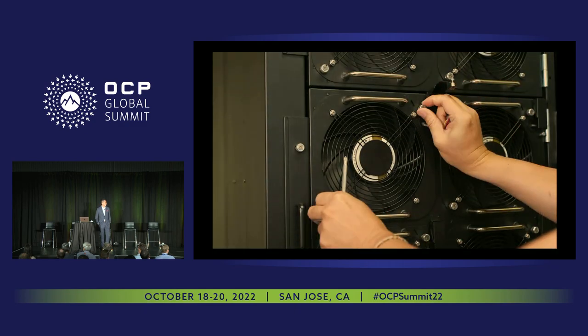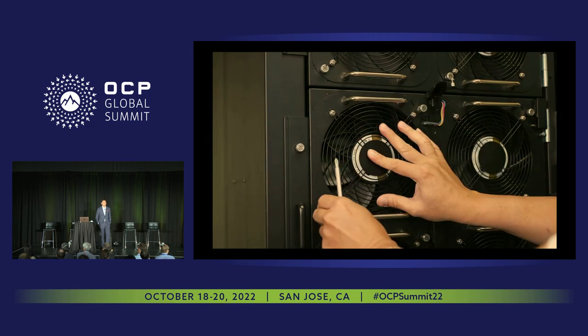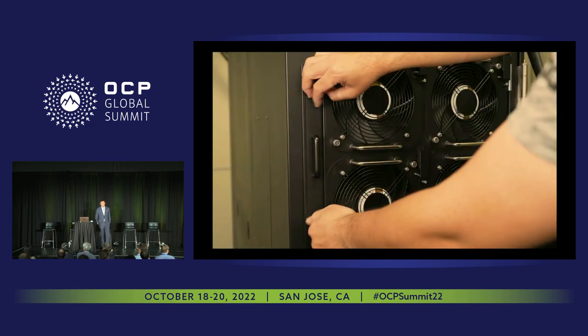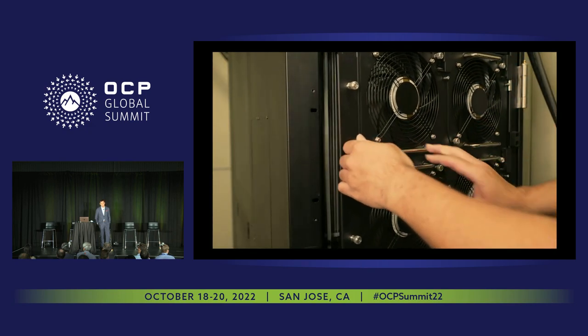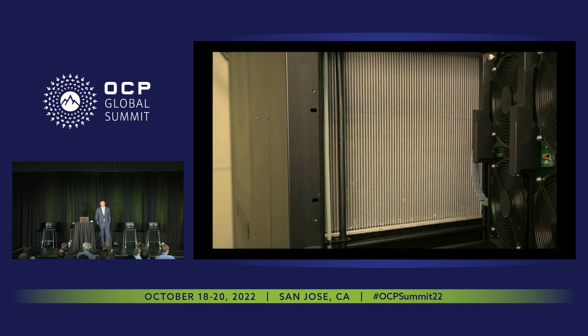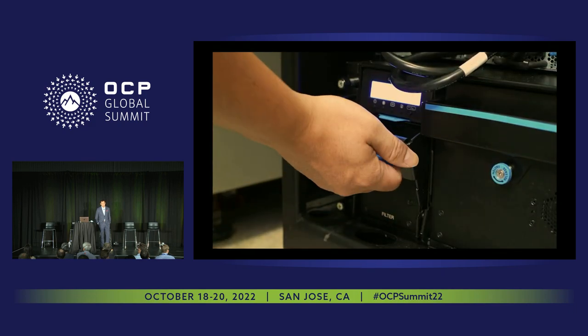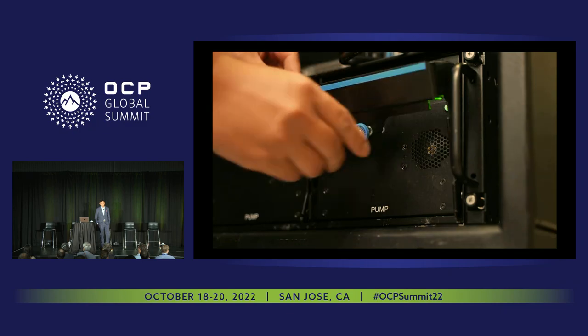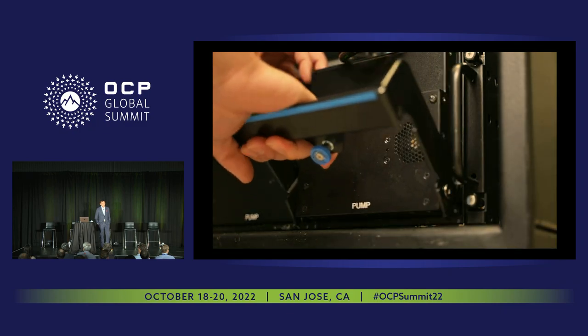And for serviceability, each individual fan can be taken out, and 4 fans are grouped into 1 fan board where each fan board can also be opened. The CDU and its coolant filter are also hot swappable, and the CDU pumps are all redundant.